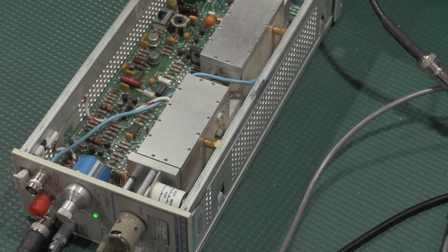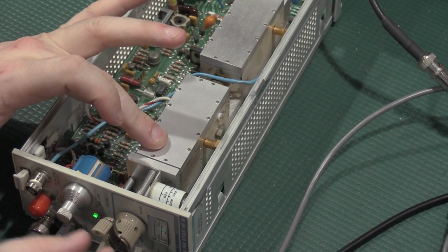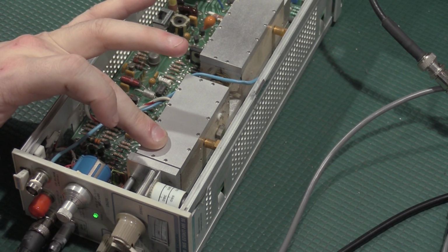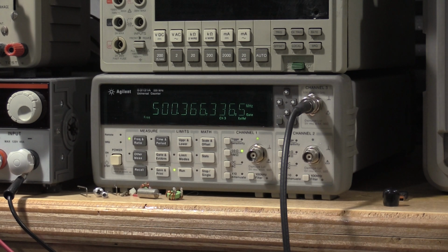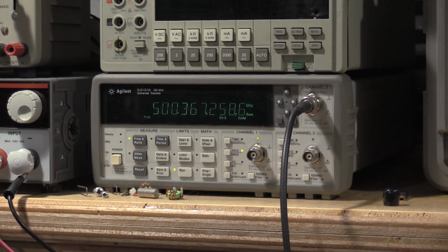Now I need to check the high range alignment. So 500 megahertz, here we go. Well, 500.36 is not too bad, and I'm allowed 2.5 megahertz. So 300 kilohertz, well within spec. All right, 1050.